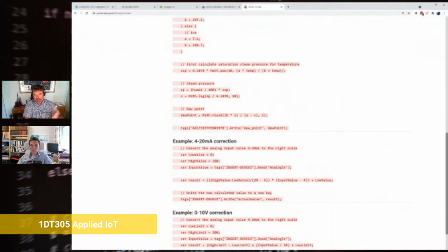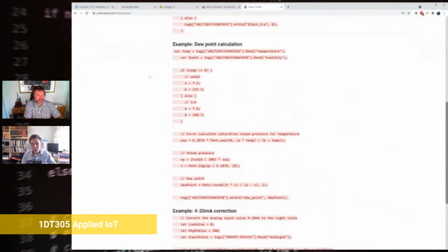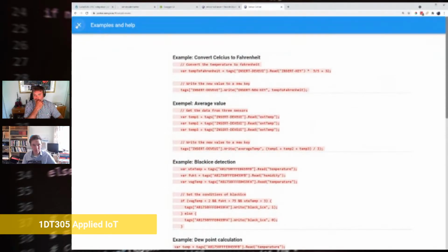Let's say many analog input devices report in 4 to 20 milliamps or 0 to 10 volts, but the measuring range could be 0 to 1000 Pascal or 0 to 2 bar or whatever. You need to present, not milliamperes to the end user, but the actual measurement he's interested in. That could also perhaps be done on the device, depending on what kind of device you have - so it's a preference.